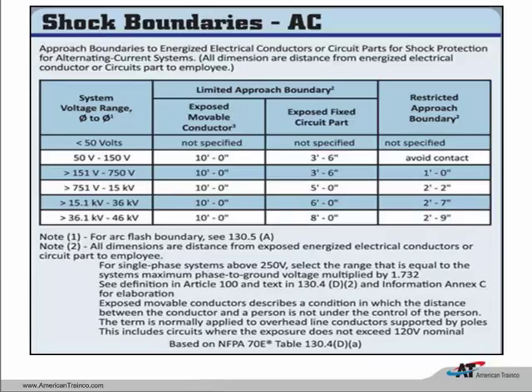That was deleted completely, so the prohibited approach boundary will be gone. They did make a slight change to these tables also as far as the voltage range is concerned. So in 2012, we still had less than 50 volts, pretty much no rules if the equipment is going to be safe. We didn't have to worry anything about shock. We didn't have to wear gloves. And the same thing here in 2015.